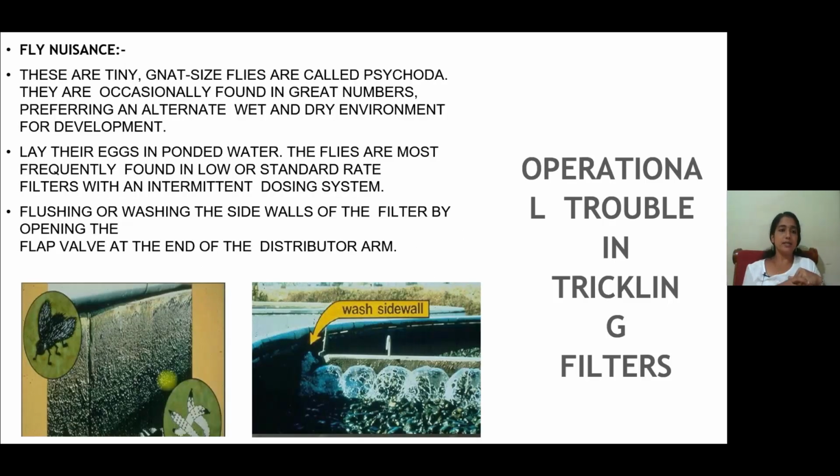Then the fly nuisance. These tiny gnat-sized flies are called psychoda. They are occasionally found in great numbers, preferring alternate wet and dry conditions inside this filtration tank.